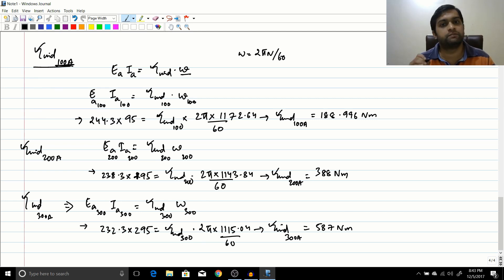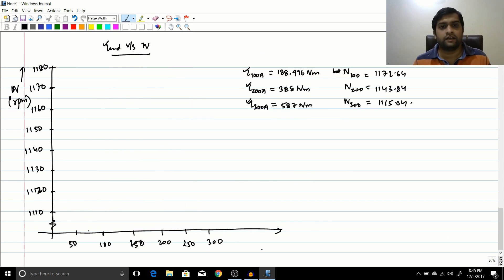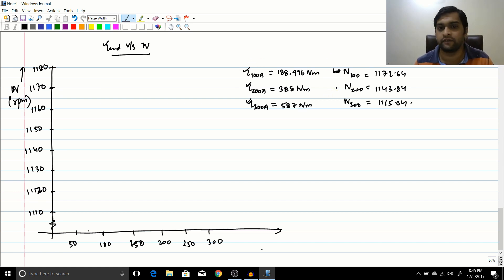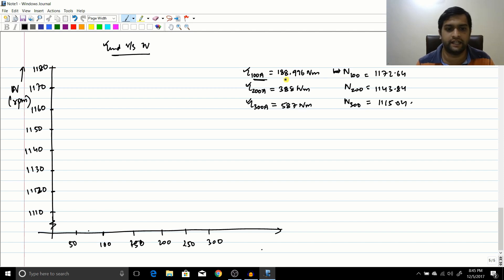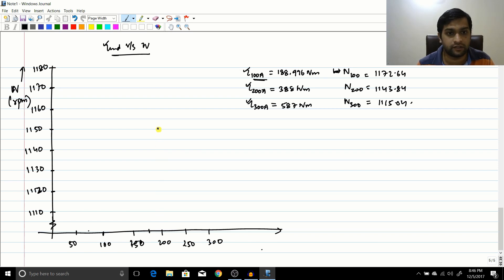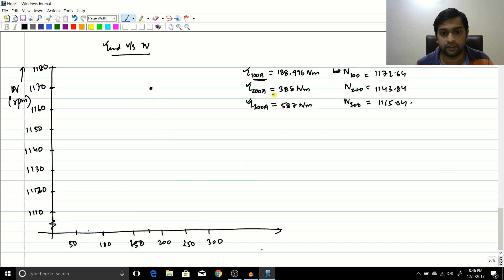Now let us draw the torque-speed characteristic for this problem. I have noted all the values. At 100 amperes, torque was approximately 188 N·m and speed was approximately 1172 RPM — that gives us the first point on the graph.